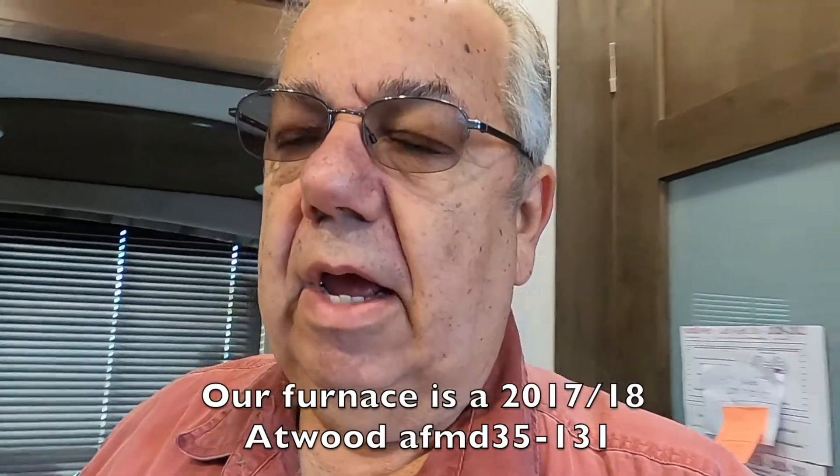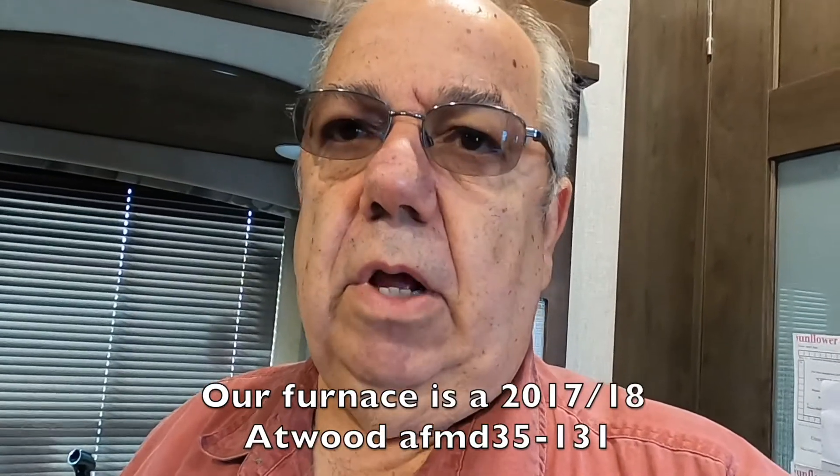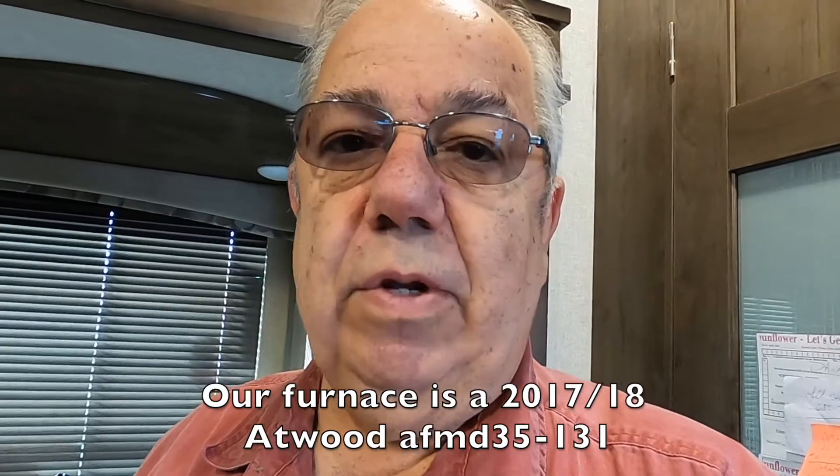What we discovered is nothing is happening now. You turn the thermostat up, you have absolutely no blower blowing. I wound up trying it out again, hitting the reset button — all there was was a flash and a click on the motherboard and that control circuit board. I started getting the one blink light after doing research. These control boards that Atwood Dometic put in their furnaces are cheap. They have a high failure rate, and they go out after so much use. The fact that we're living in this thing, it didn't last that long — the rig is a 2018, so about four years.